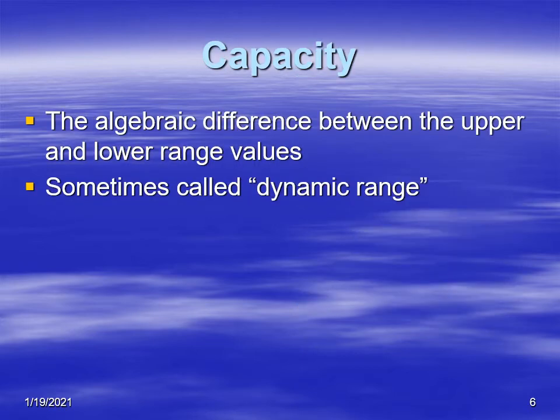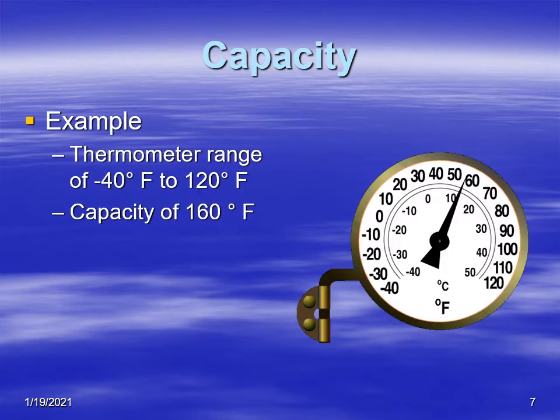Capacity is similar to range in that it measures the distance between the upper and lower values, but it does that in terms of a difference. The difference between the upper value and the lower value is considered the capacity, and sometimes it's called the dynamic range. Going back to our bimetal thermometer, the top was 120 and the bottom was minus 40. The difference between those is 160, so the capacity of this thermometer is 160 degrees Fahrenheit.